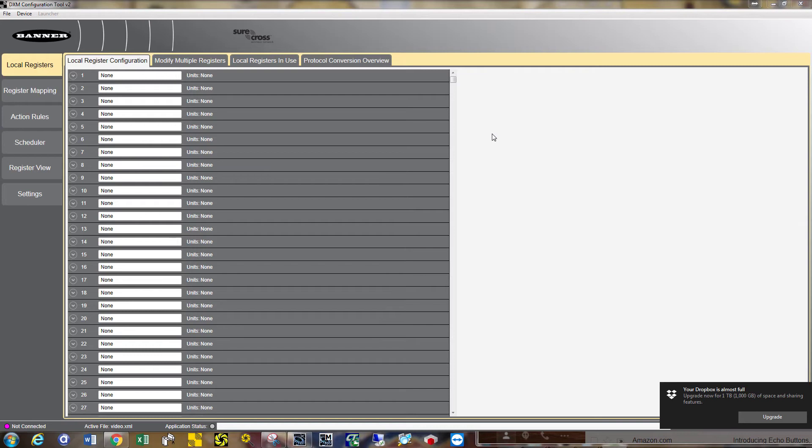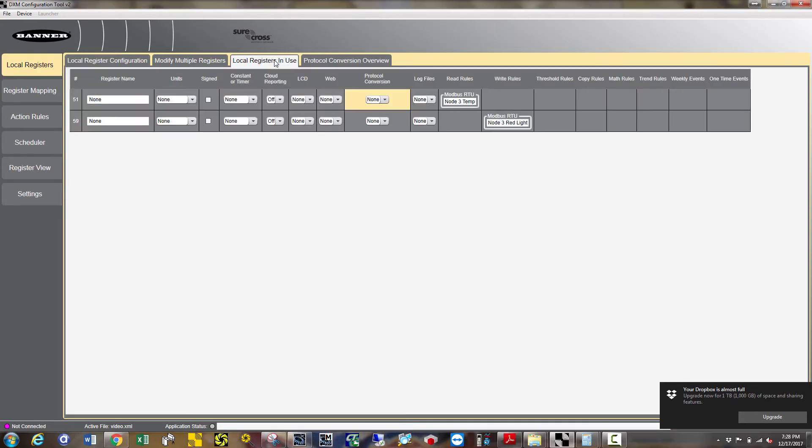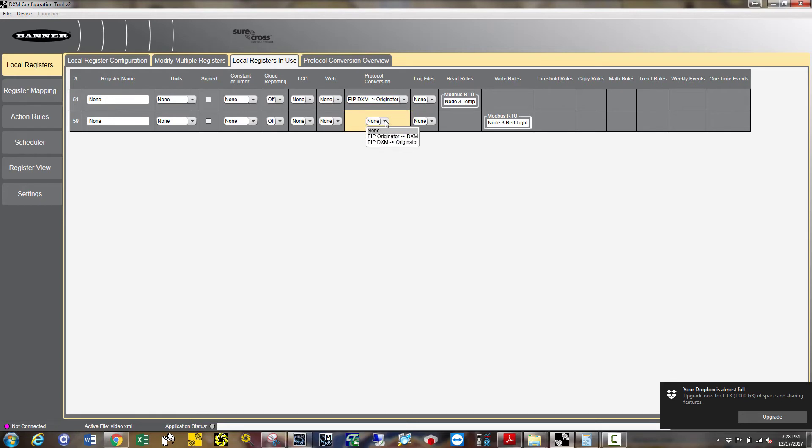The final step is to go to the tab local registers in use. Under the protocol conversion, for register 51, choose EIP DXM to originator. Then under register 59, choose originator to EIP DXM.